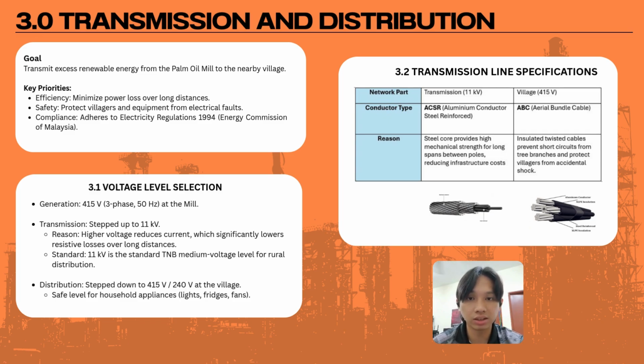First, let's discuss our voltage strategy. We generate power at 415 volts, however, to minimize massive power losses over the long distance, we step this up to 11,000 volt. We choose 11,000 volt because it is the standard TNB medium voltage level for rural areas. Higher voltage reduces the current, which significantly lowers resistive losses in the lines.